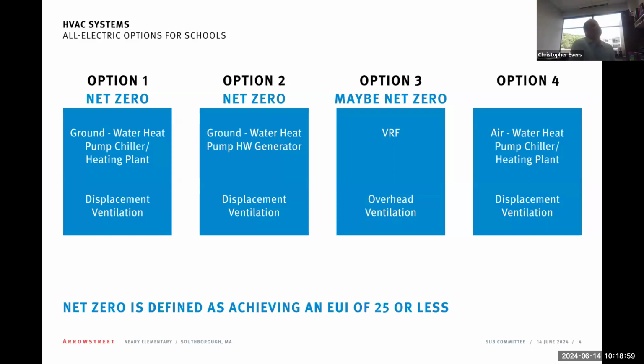Yeah, so I've seen a couple recent projects where obviously the boilers are secondary, where you're injecting heat into the loop on those really cold days. A heat pump system loses its efficiency when it gets cold outside, because the ambient air temperature is so low that some of the systems are derated in 0 degree weather and below. Most systems can go down to -14, and some are even getting more than that, but you do lose efficiency on the heating side, so you have to supplement with electric heat. I know you talked about cost, and electric boilers. I've seen the required electric consumption on those. I've looked at a couple of projects where we need to almost bring in a whole new service, so that electric boiler would only be supplemental, just to increase the temperature. It would be supplemental, yes.